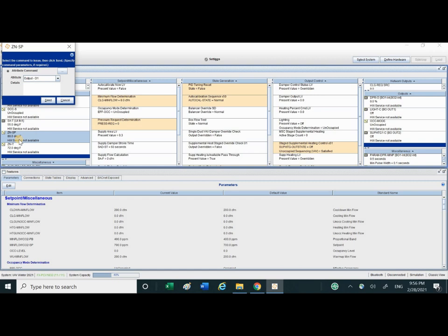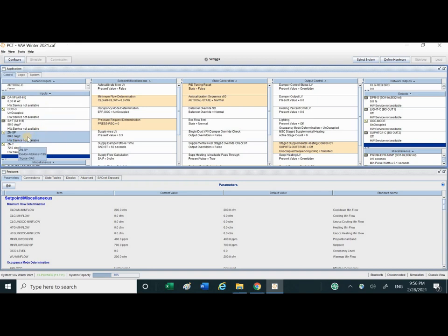Then we change it to lower temperature. And then suppose we set to 60 Fahrenheit degree. Then set it. So we change the set point from 80 to 60. So the set point is lower than the room temperature. So the heating should be off. You can see here it's off. And here the lighting is off. Now it's off. And you see the damper, it's closed.